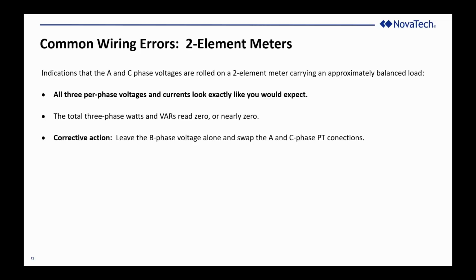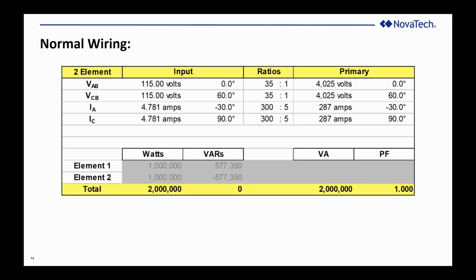So leave the B phase voltage alone and swap the A and C phase conductors on their PT terminals on the wattmeter. Here's your normal situation, and here's what happens if I reverse them. Notice in this case, I'm just switching the 60-degree phase shift on the VAB and the 0-degree on the AB and the 60 on the CB. I'm switching the 2 of them in the error condition, and both the watts and the VARs add up to 0.